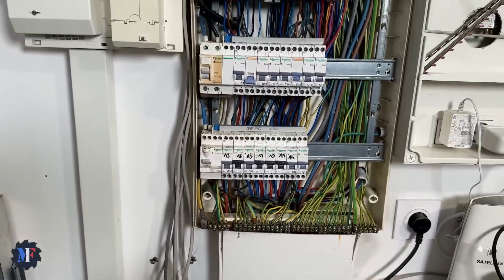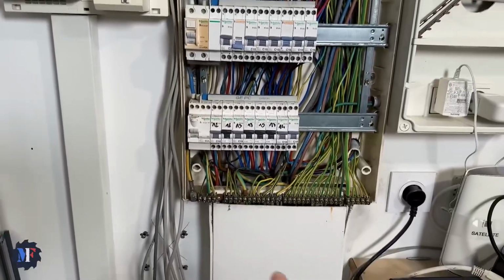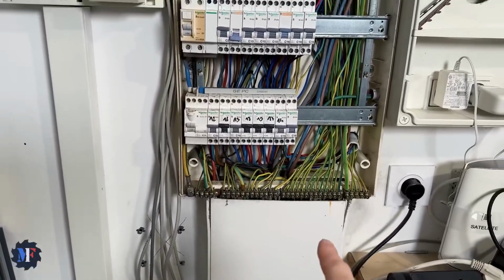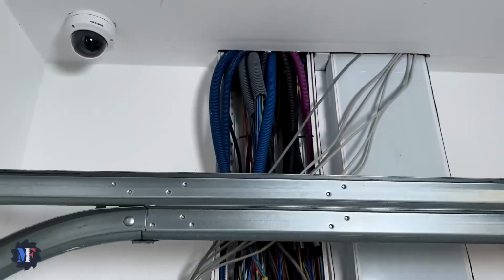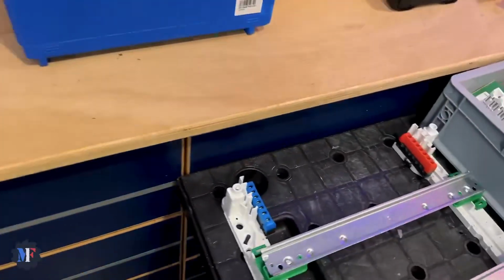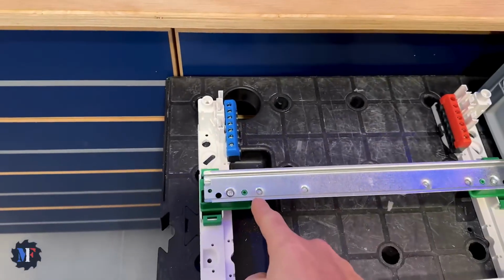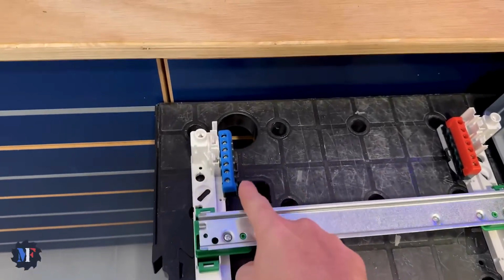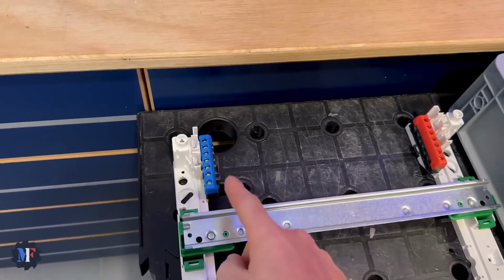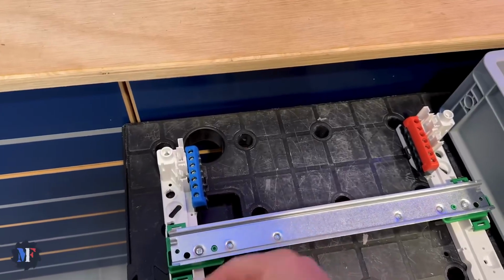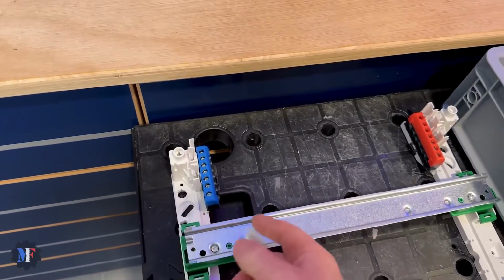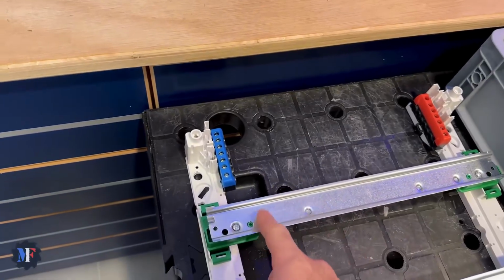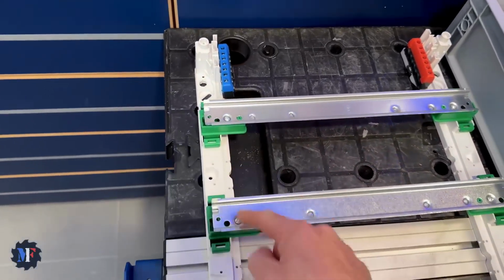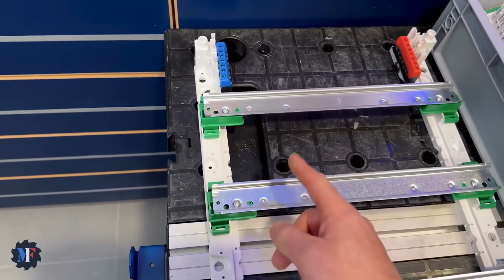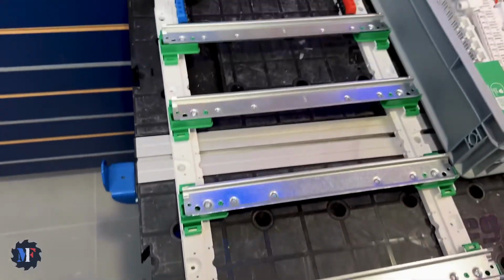Well, for my secondary panel, it's going to be exactly the same, except that instead of having the ride-in here, we'll go back into the attic. And we'll tap either directly into the interdifferential or into the terminal block. I prefer the terminal block method because if I ever need to reconnect, I know my terminal block is powered. Otherwise, you can power the interdifferential directly, which will then drive the second one via a vertical comb. I'll show you that in a moment, the 3rd, the 4th, and so on.